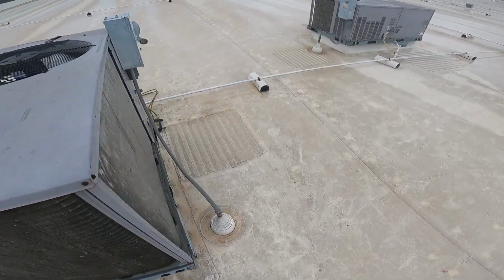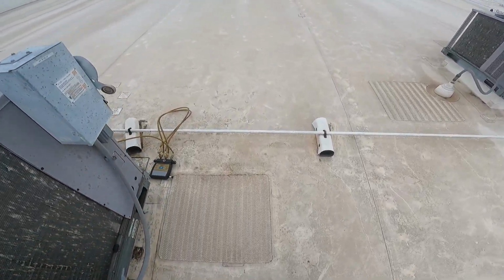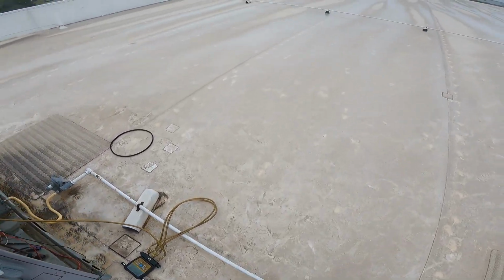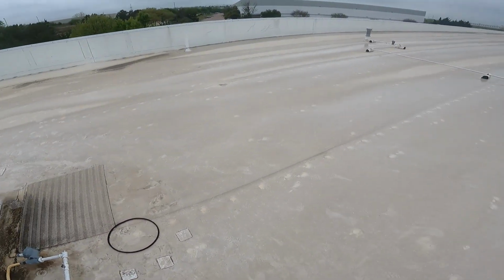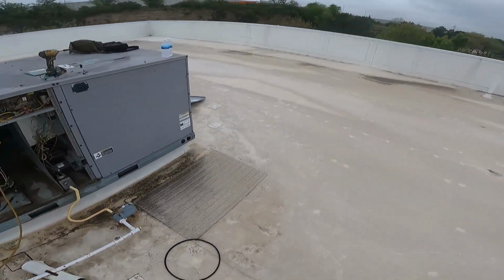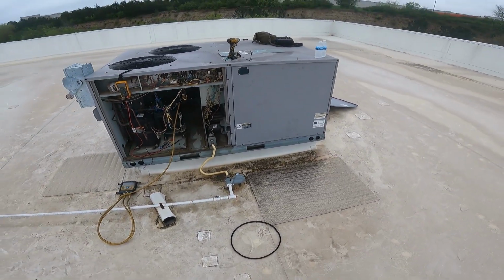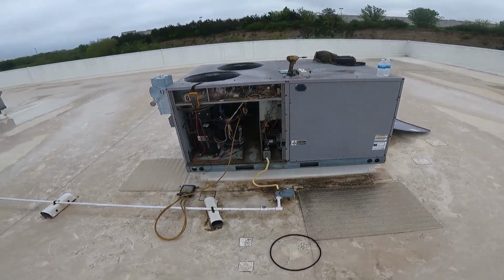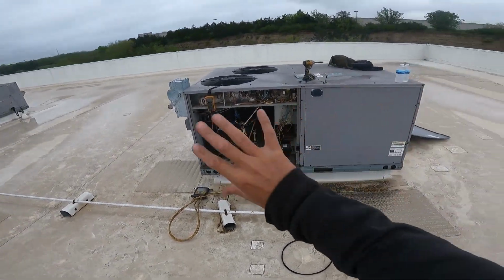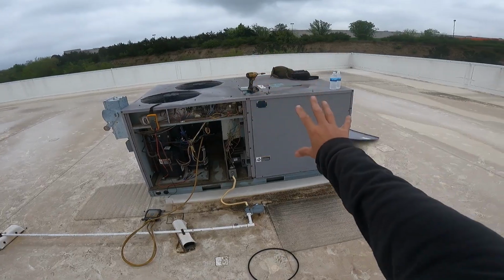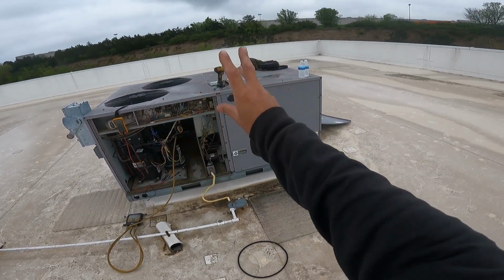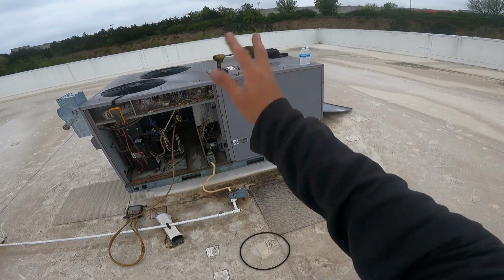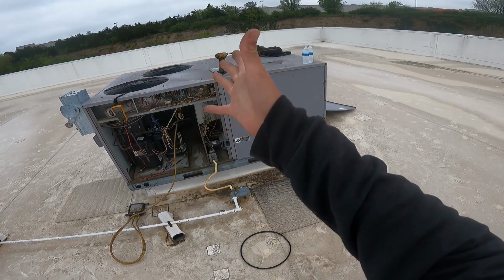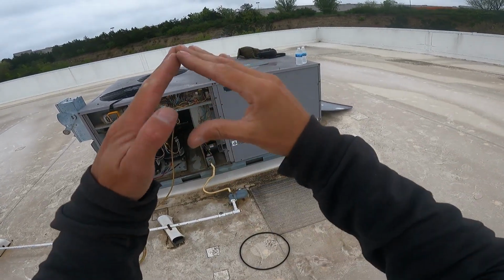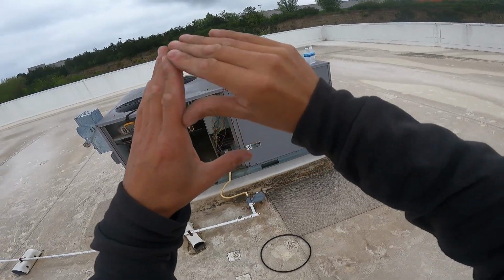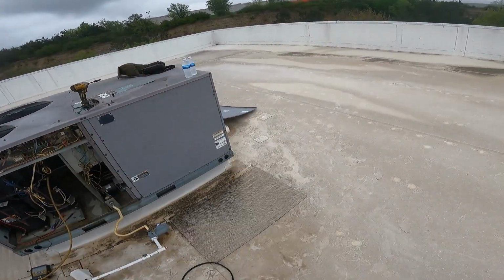This is R22, which we can come back with some R407C, or some R438A, or some NU22, whatever replacement refrigerant you want to use. I'm kind of partial to 407C for HVAC, for an AC unit. Now if it was refrigeration, R407A — not the C, A. Yeah, that's A. That's whatever.